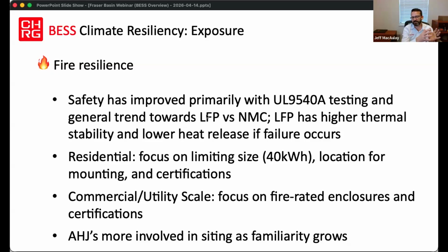So it used to be only at a small scale that was true. Now even the large scale BESS units are mostly all LFP for safety purposes, just because it has a higher thermal stability. To be plain about it, it takes a much higher temperature to cause the battery to catch fire if the fire source is external. And then there's a lower overall heat release if the failure occurs, which could cause less overall structural damage and be able to be put out a little bit easier.